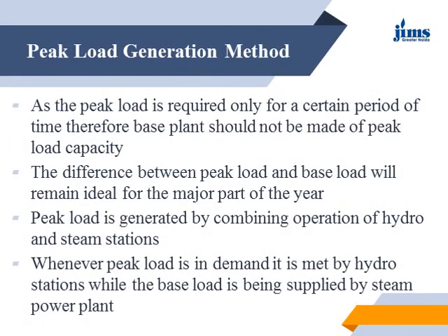So how can the peak load generation be maintained? As the peak load is required only for a certain period of time, the base plant should not be made for the peak load capacity. Why should we waste our money and time making such a plant to cope with the peak load capacity? The base plant or big plant should be made for the base load, and then some additional plants, like open cycle gas turbine or closed cycle gas turbine plants, may be used to cope with the peak load requirement. The difference between the peak load and the base load will remain idle for the major part of the year.